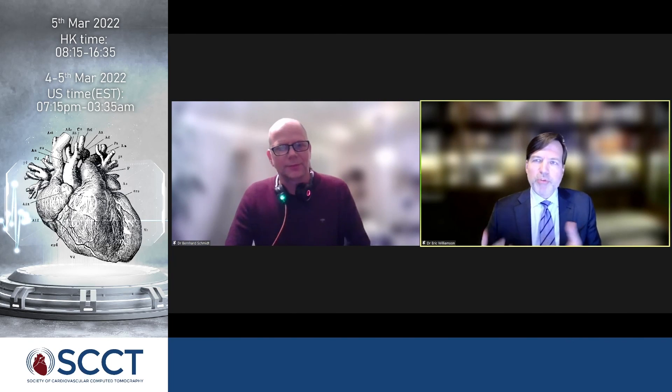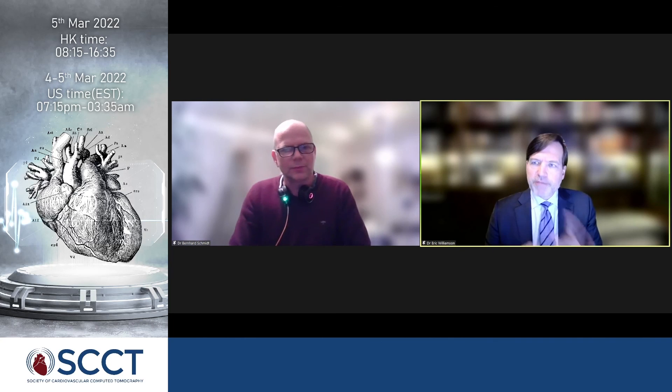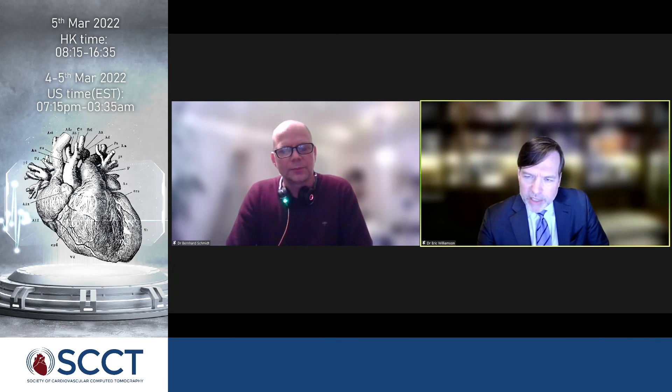Eric: So there is actually a real difference in resolution resulting from the difference between the photoelectric and Compton effects? Bernhard: Yes — similar to iodine as a high atomic number contrast material, which also predominantly undergoes the photoelectric effect, causing immediate interaction and deposition of all the energy. That is of benefit from a detector perspective.